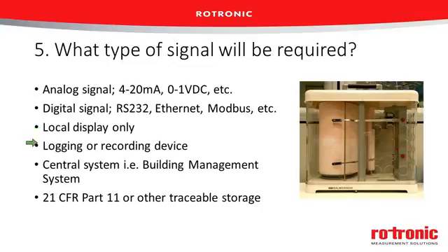Quite often, we actually do want to have some sort of logging of the recording or of the readings. This is very common now. We'll see this in data loggers. They'll have significant built-in memory. Even transmitters will often have some memory there. And this would then come out of the device using digital signals. So this relates back to something that's going to have some type of digital communication.